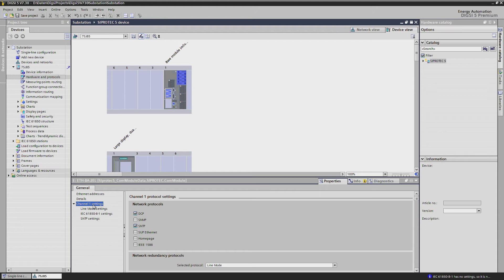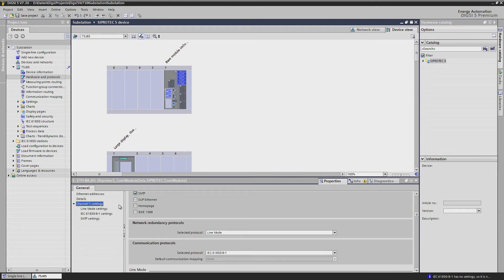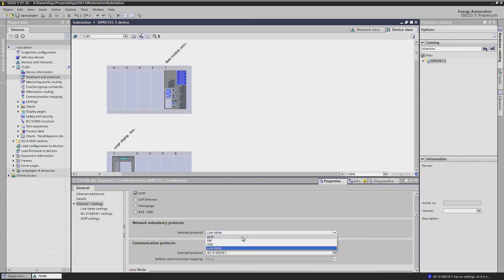In the middle block, you have the choice to select various communications topologies, like a redundant point-to-point connection, line mode, or RSTP — the Rapid Spanning Tree Protocol — using the built-in switch functionality of our communications modules, allowing you to connect up to 40 devices in one communications ring. Or one of the seamless redundancy protocols, PRP and HSR. We are going to use RSTP.